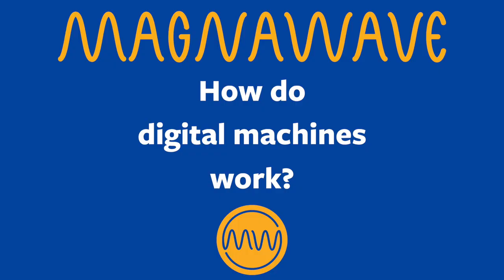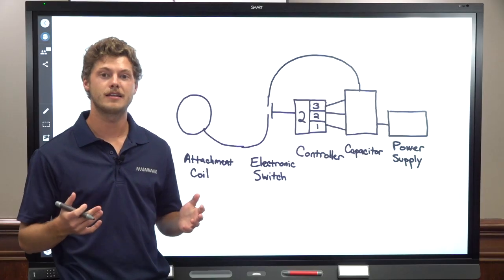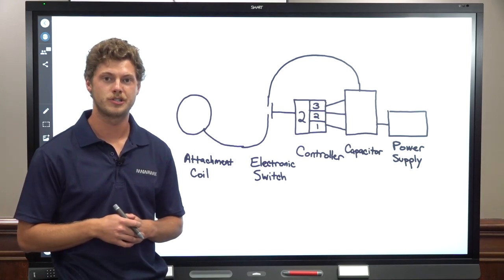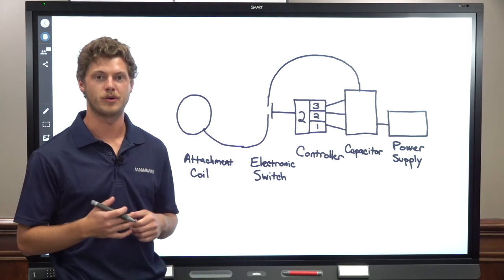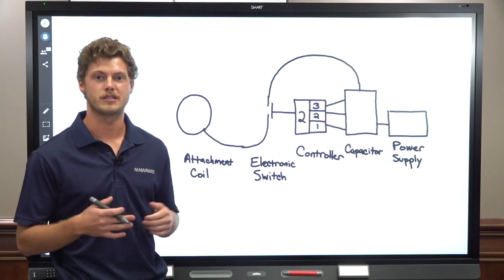Digital machines do not use spark chambers to control their pulsing. Instead, they use an electronic switch and a controller to actuate each pulse. But all of the rest of the basic components are the same.